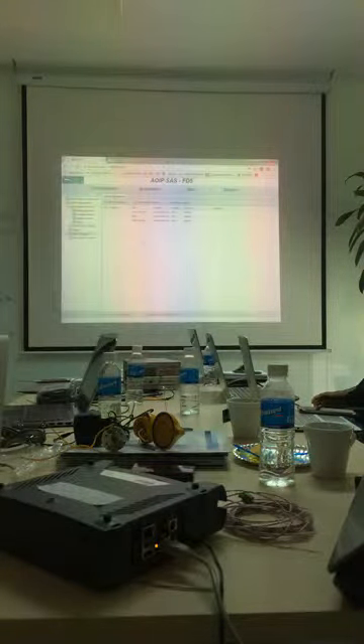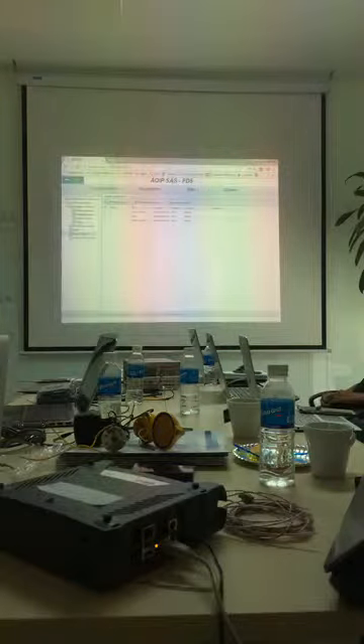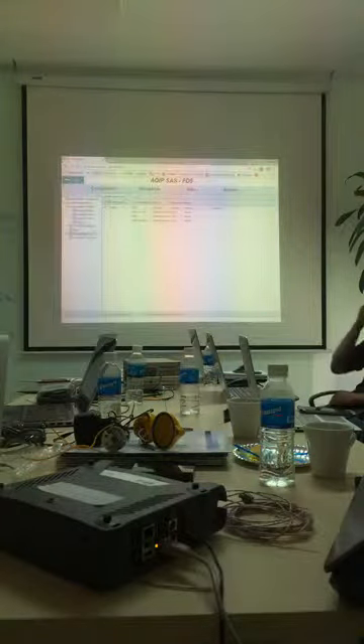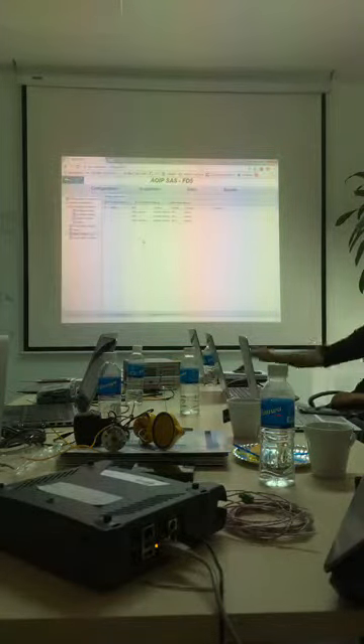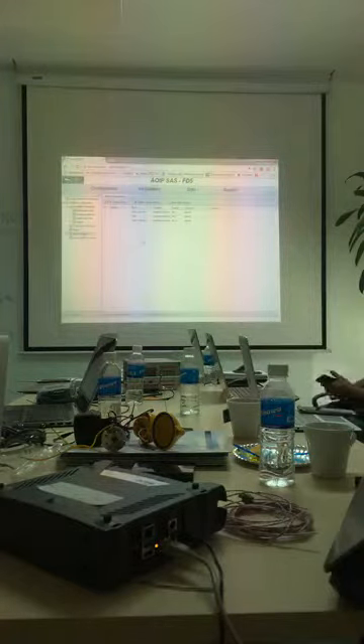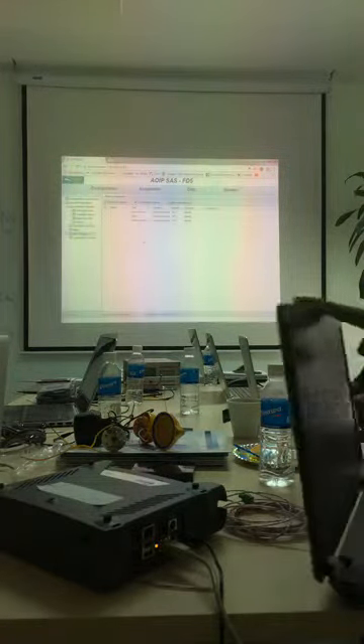So that means it will be only informative measurement, and the guy would have to come to connect the laptop and to check what will be the subject of the alarms. But you can configure alarms without any information, without any signals. The purpose of configuring an alarm is that when you download the data after your acquisition, it will be indicated: alarm triggered. Most of the time, people keep one relay. They don't know which alarm was triggered, but for a highly important process, it's important. They inform, they can come.